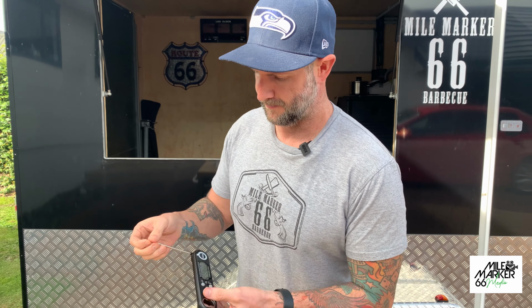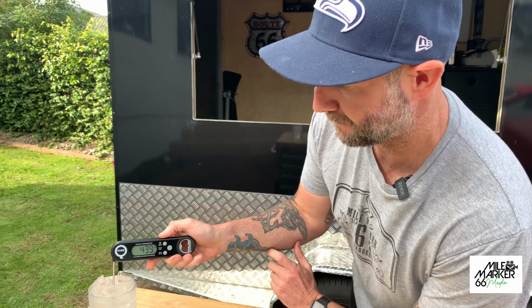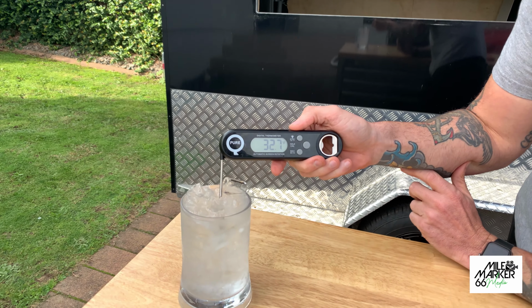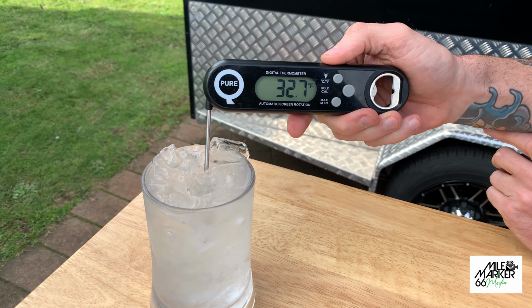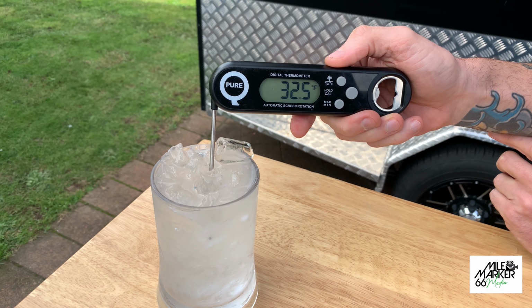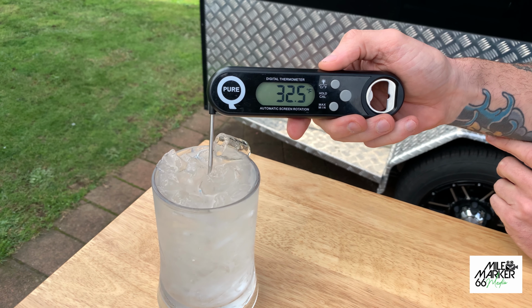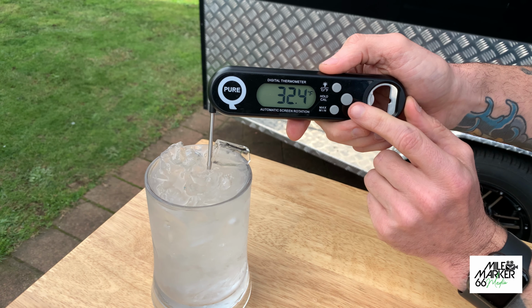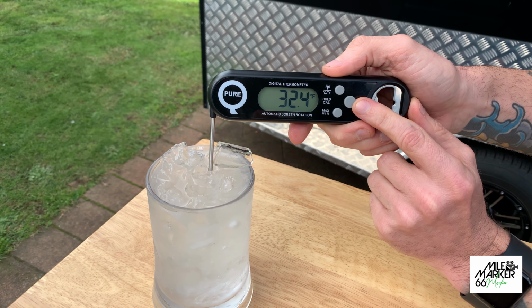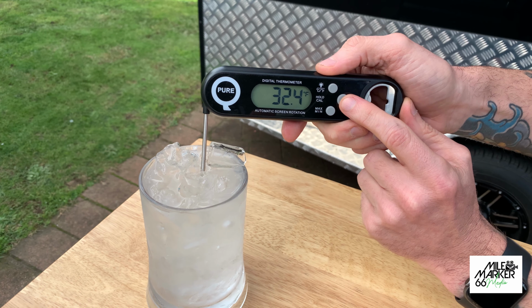Next up's our PureQ. Now we can both validate and calibrate this one. And it is reading reasonably accurate. I gave it a bit of a calibrate before just as a trial run, but we'll put it in and we'll show you how to go through it regardless. So you can see there, it is quite accurate and very fast to respond also. The way that we do a calibration here is that we hold down our calibration button, and that's going to put us into calibration mode.